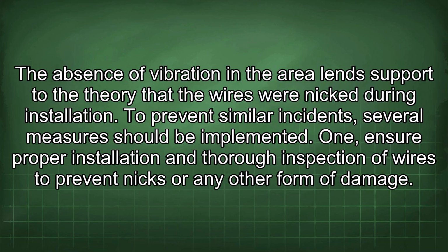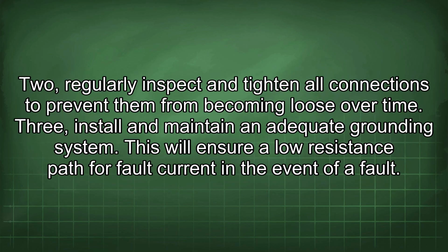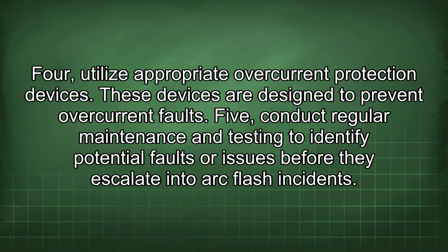1. Ensure proper installation and thorough inspection of wires to prevent nicks or any other form of damage. 2. Regularly inspect and tighten all connections to prevent them from becoming loose over time. 3. Install and maintain an adequate grounding system. This will ensure a low resistance path for fault current in the event of a fault. 4. Utilize appropriate overcurrent protection devices. These devices are designed to prevent overcurrent faults. 5. Conduct regular maintenance and testing to identify potential faults or issues before they escalate into arc flash incidents.